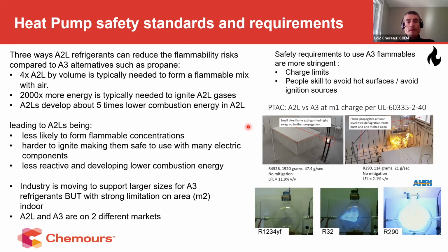When you look at this risk of flammability, you would require about 4 times the volume of refrigerant A2L to be equivalent to the flammability that is achieved by an A3. So this is the reason.